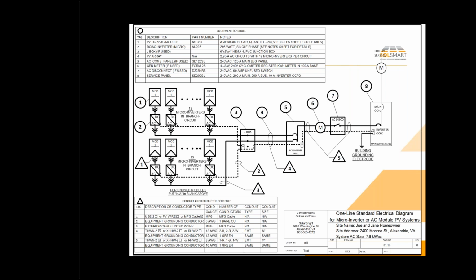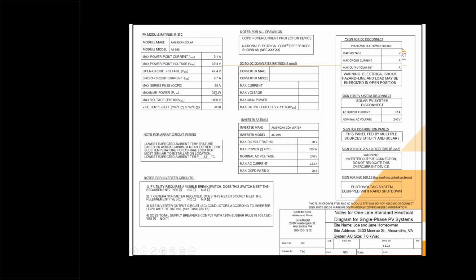Again, the largest residential system that you could put on a 200-amp panel following the 120% rule guidelines of Article 705. Here's the details, same module, different inverter. You can see that instead of 32 amp output, it's got a 1.23 amp output. And then we don't have a DC disconnect sign because it's a microinverter system. All we have is the AC PV system disconnect sign. And again, the panel fed by multiple sources, utility and solar, don't relocate the circuit breaker, and it does comply with the rapid shutdown.